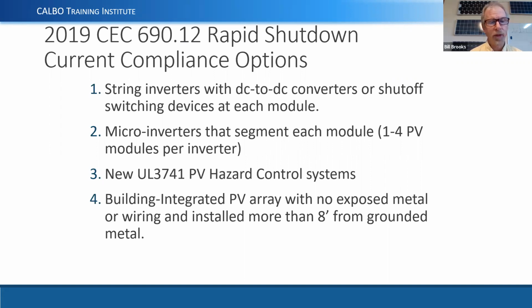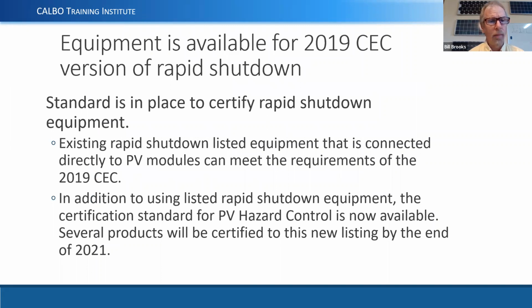This new UL 3741 PV hazard control is still an option and will be for building integrated PV arrays with no exposed metal and installed more than 8 feet from grounded metal. Very difficult to comply with that, by the way, but it is still an option, and it is in the code. So the standards in place to verify rapid shutdown equipment. So we have rapid shutdown listed equipment. All of our inverters are going to have listings for rapid shutdown. Microinverters are going to have it, things like that. And then there might be a combination of listed rapid shutdown equipment used in a PV hazard control system.